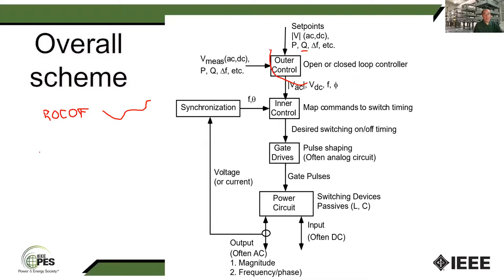Another one they'll do is look at rate of change of voltage magnitude. It's another scheme that a lot of inverter manufacturers use. There are a number of other schemes that inverter manufacturers use. Some are passive schemes like this. They also have some active schemes where they periodically inject their own variation in real power and see how the system responds. If they put that injection in and see a change of frequency as a result, they know that they're disconnected. They may do those fairly often, especially if the frequencies are already moving around. So that's an example of an active scheme. Most of the vendors prefer passive schemes, but passive schemes are less reliable.